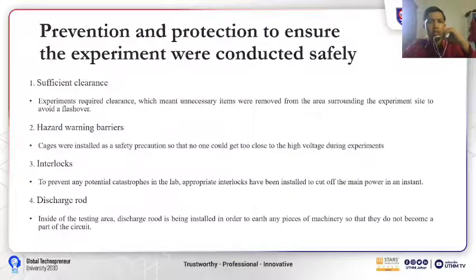Next, for the prevention and protection to ensure that the experiment was conducted safely: first, sufficient clearance. The experiment required clearance, which means unnecessary items were removed from the area surrounding the experiment site to avoid a flashover. Second, hazard warning barrier cages were installed as a safety precaution so that no one could get too close to the high voltage during the experiment. Third, interlock. This is to prevent any potential catastrophes in the lab.